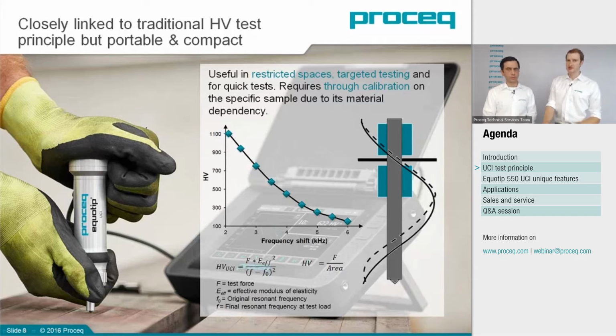You can see this also in the formulas of the two principles, shown right below the chart. On the left side is the one for UCI. Beside the test load and the frequency shift, there's also the value of the elastic modulus in the formula, so it also has an effect on the measured hardness value.